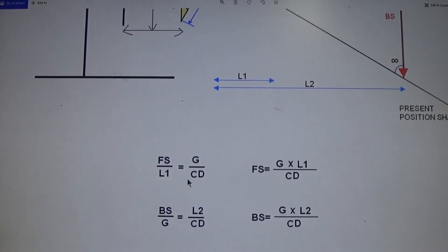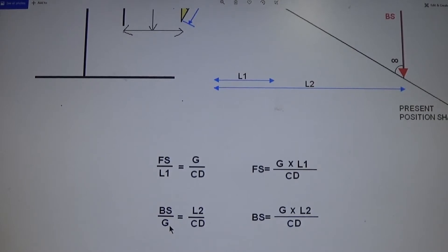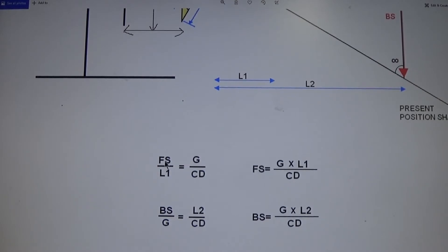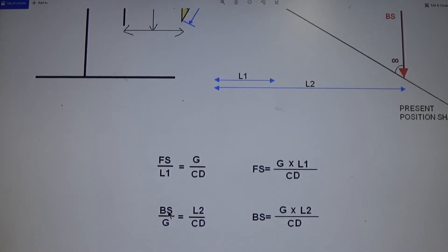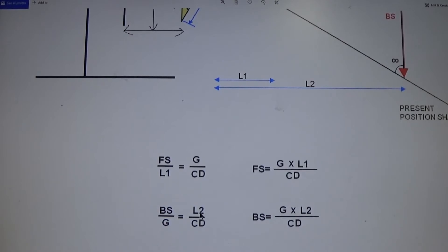You can write the equation: FS over L1 is equal to G over coupling diameter. From here, FS equals G times L1 divided by coupling diameter. The same relationship holds for the back side: BS over G equals L2 over coupling diameter. FS is the amount of shims to add or remove from the front support, BS is the amount for the back support, L1 is the distance from the coupling hub face to the front side, and L2 is the distance from the coupling hub face to the back support.